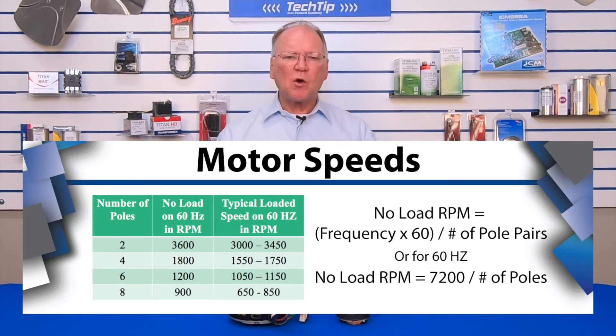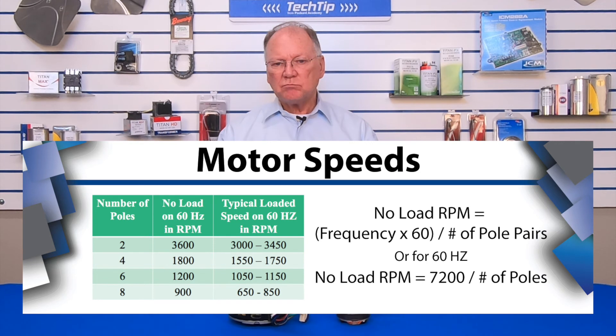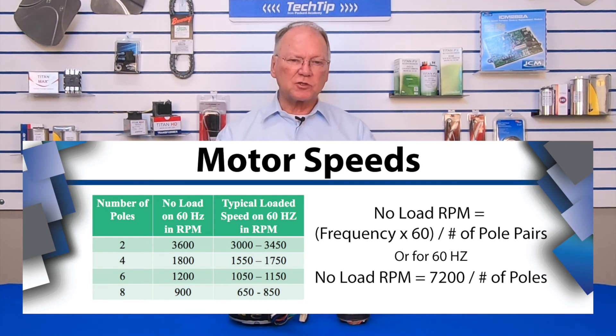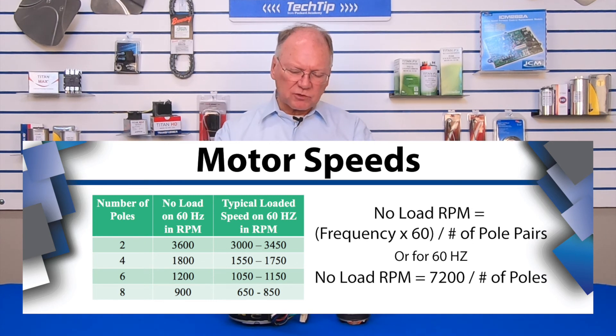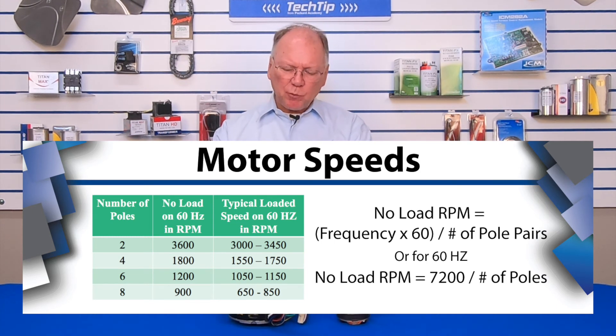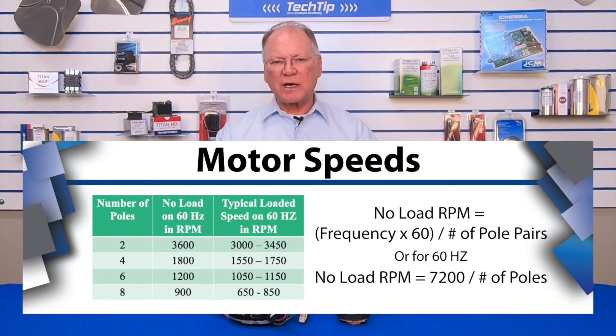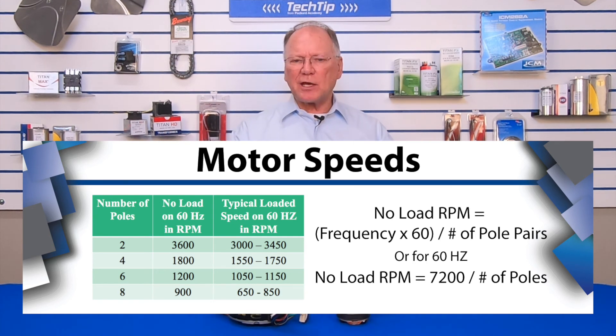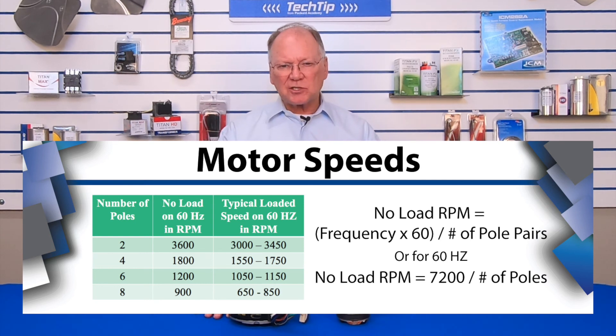Comparing that to this table, the far-right column shows the typical speed a motor achieves when it has a load on it. A four-pole motor could operate at 1725 RPM or 1650 RPM — somewhere in that range. A six-pole motor is where our 1075 RPM motors are, so this particular motor is a six-pole motor. If it were an eight-pole motor, the nameplate would probably show 825 RPM.